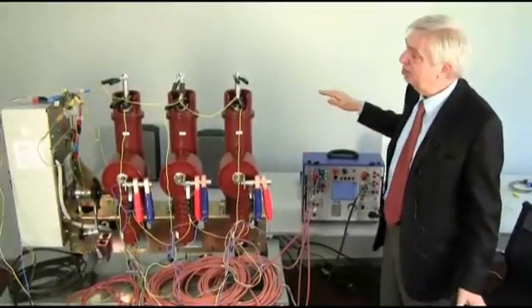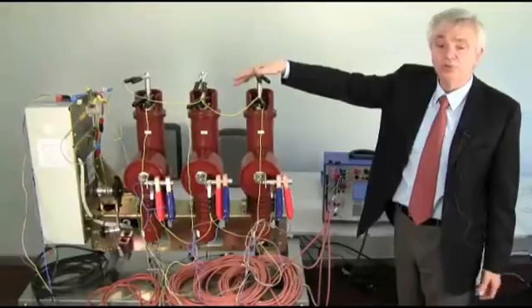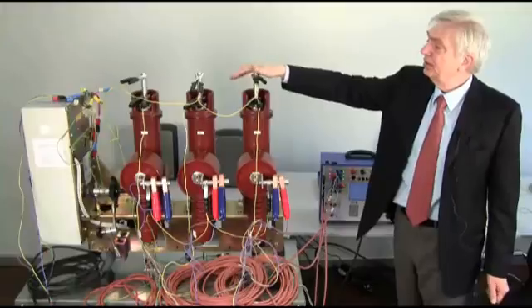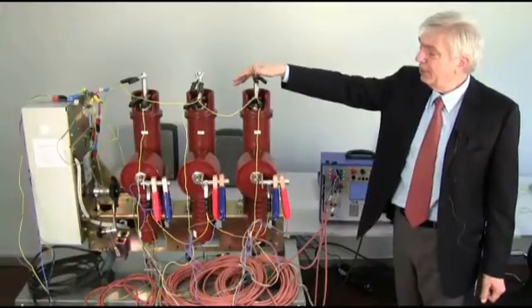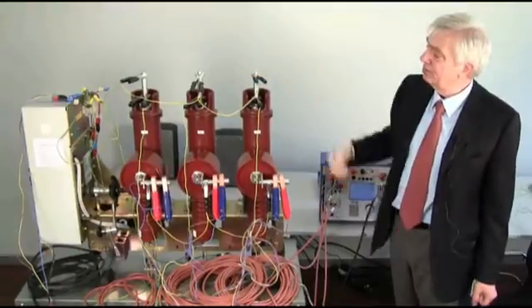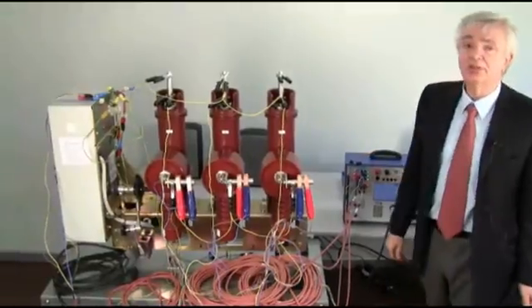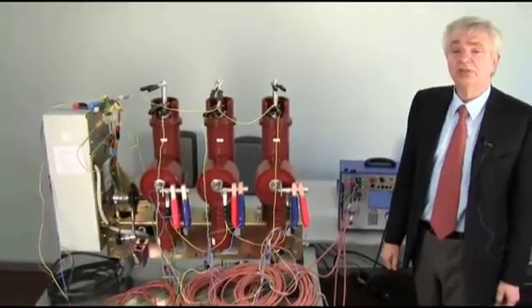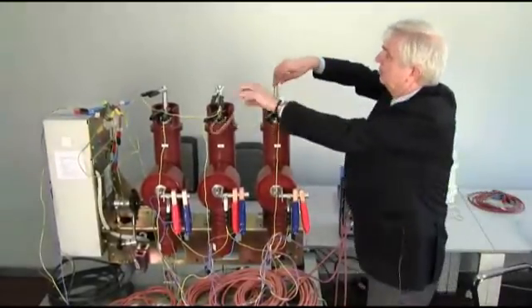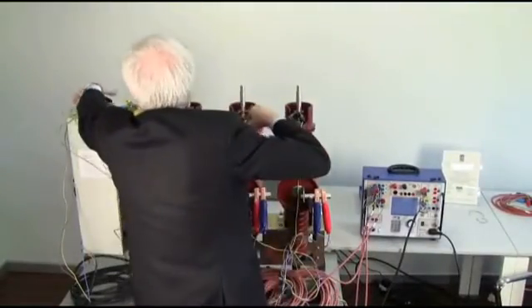So, now you are ready to operate and before starting you have to remove the grounding on one of the two sides of the circuit breaker. About this operation that puts some degree of unsafety on your testing, we will discuss later on when we will discuss the both sides grounded option. Anyway, what I am doing now is I am removing the grounding on one side.